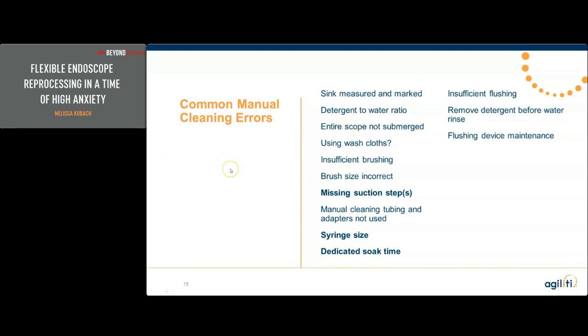Another thing I want to say, though, for the departments, usually sterile processing, that may use a syringe for manual flushing: syringe size does matter. I find a lot of extremely small syringes out there that should be 30 cc or 60 cc. This is mostly found with the urology models because they don't need a flushing tubing and they have a luer adaptation to the port.